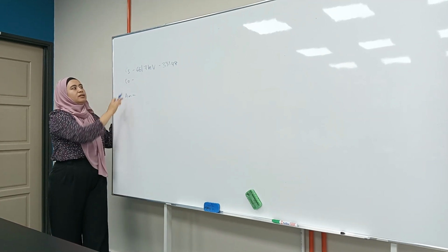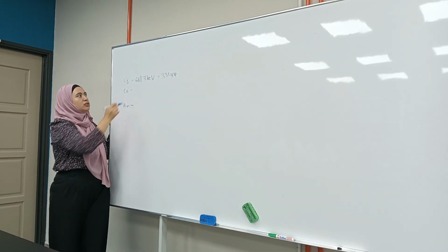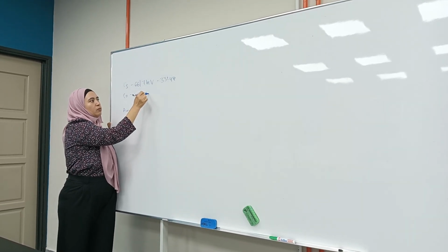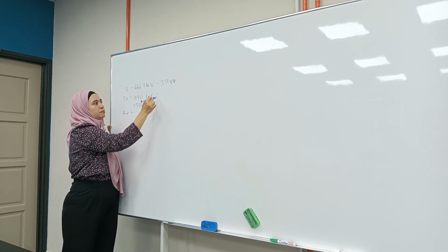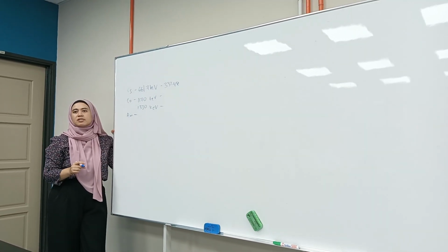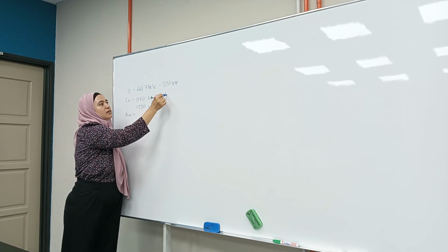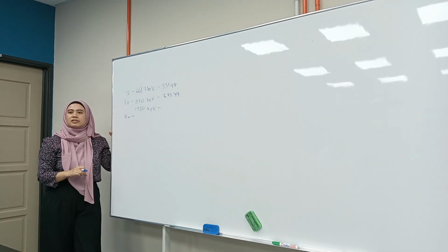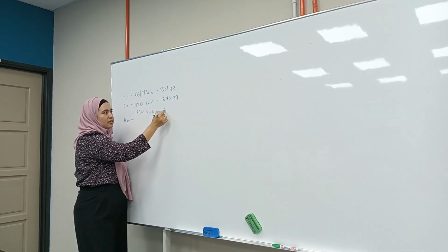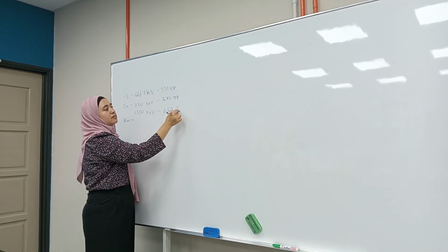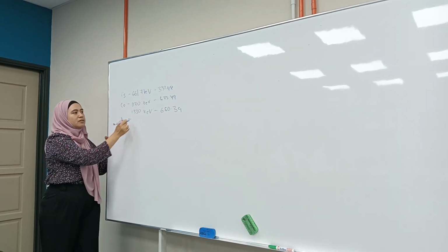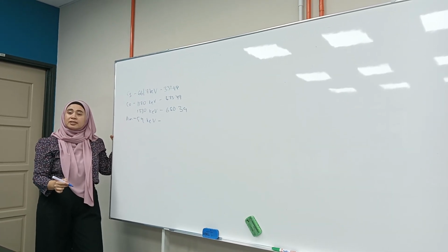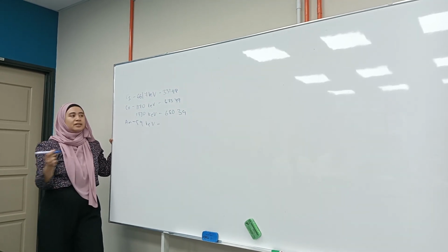Then we moved on to cobalt, and there are two peaks, 1170 and 1330. And what was the photoelectric peak channel number for 1170? 573.79. And then for 1330? 650.39. And then americium is 59. And the channel number? 34.08.